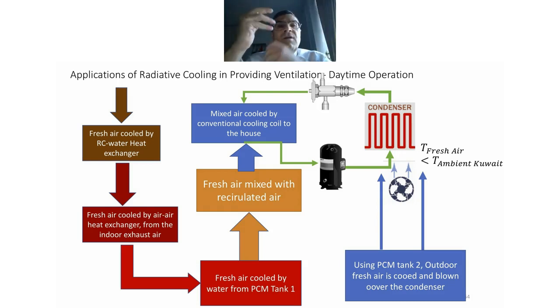We have supply and return. So the return from the room, instead of throwing it outside, we pass it over the supply in a heat exchanger way to cool it down. It is at 24 degrees C. So we further cool the air after leaving heat exchanger 1 by the heat recovery system. The cool air then flows into a third heat exchanger for cooling with the water exiting PCM1. So tank 1 is cooling the air further. So in three different stages the air is cooled: one from the radiative cooling water, two from the heat recovery, three from the heat exchanger for PCM tank 1.